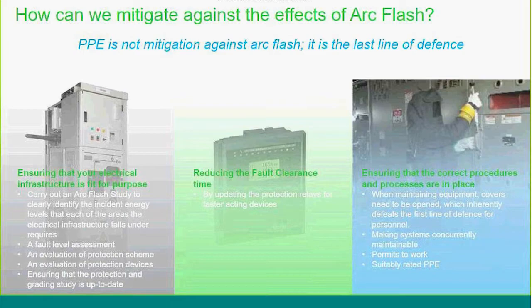So in America, one of the common practices is to have a maintenance switch. That maintenance switch selects a different set of protective device settings to ensure you have a much, much faster clearance time for faults whilst you're in the substation. So you only minimise your discrimination risk when you're in that facility in front of that equipment.